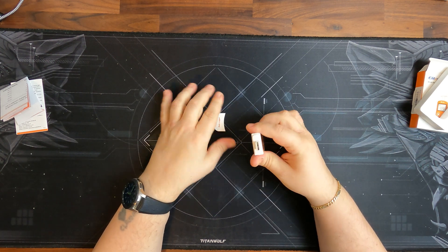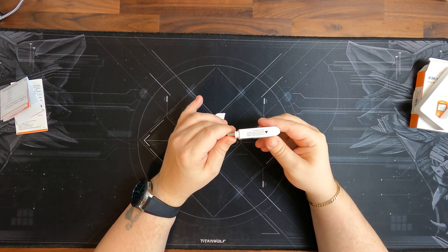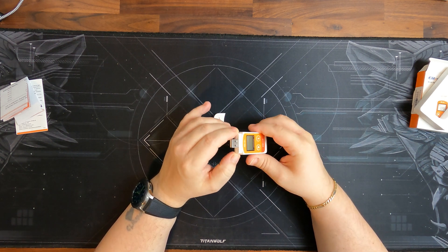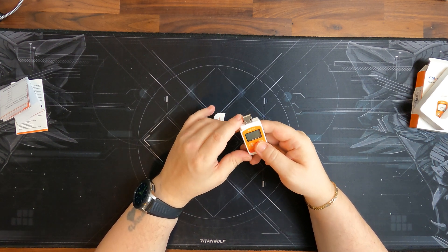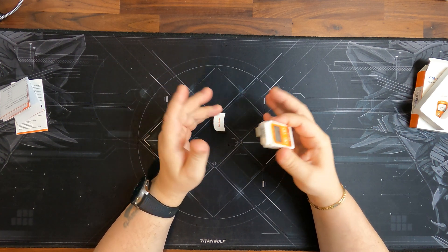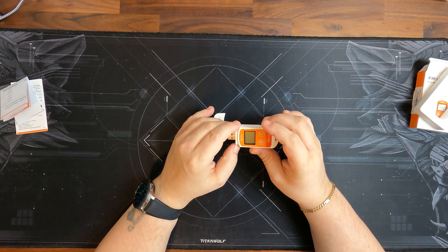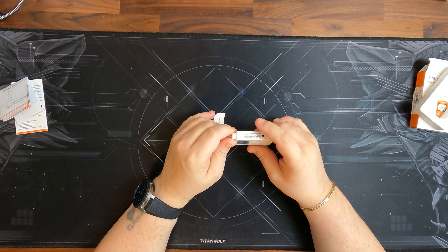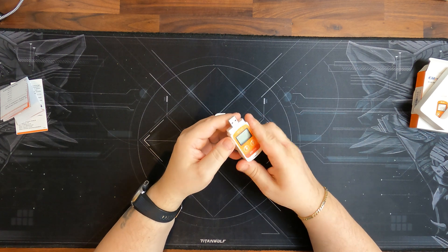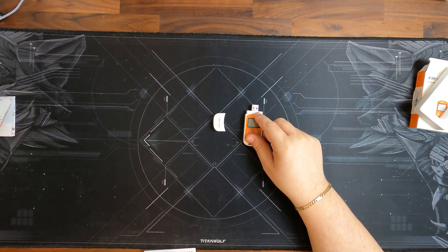When we remove the cap, we have a USB port which we can directly connect to the computer. When you connect it after turning it on and then off, it will open as a data drive and you can export the PDF file. It is recommended to download the software from the website, where you can set up certain settings like the recording interval. You can do that with the buttons as well, as described in the manual, but it is way easier with the software.